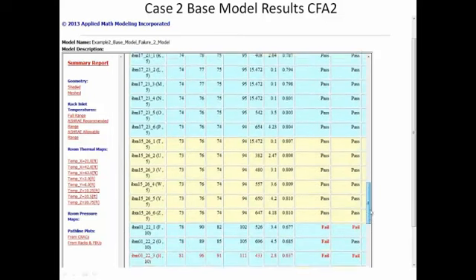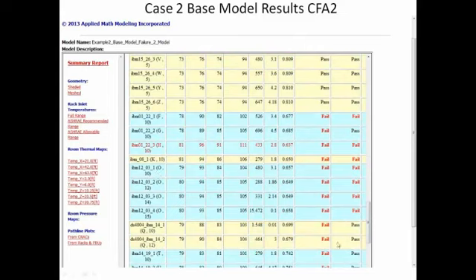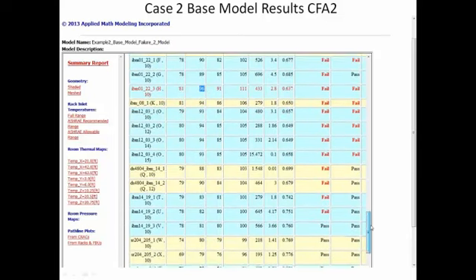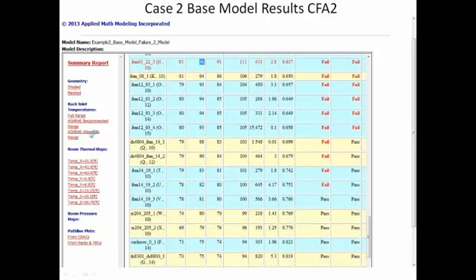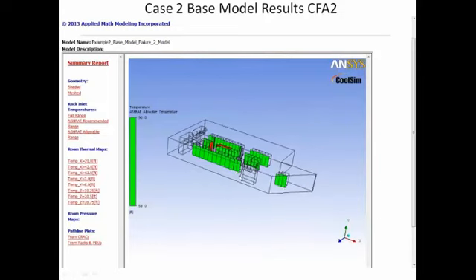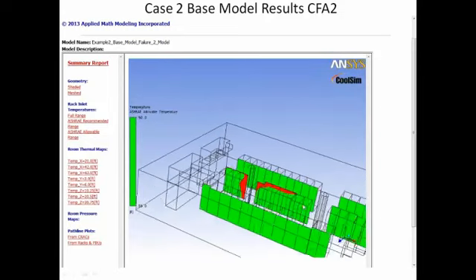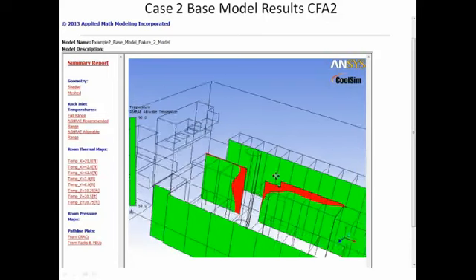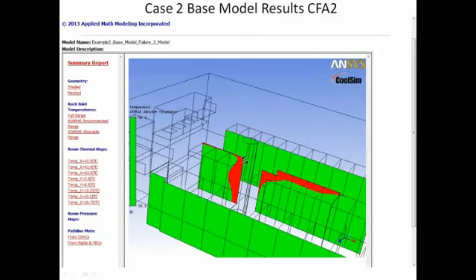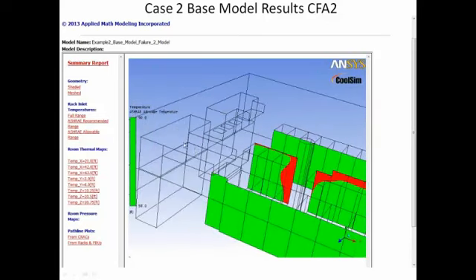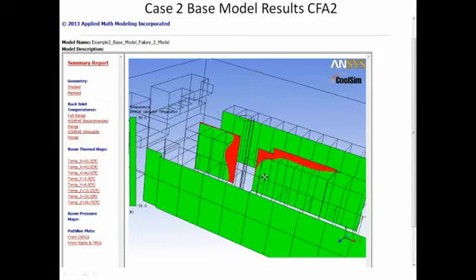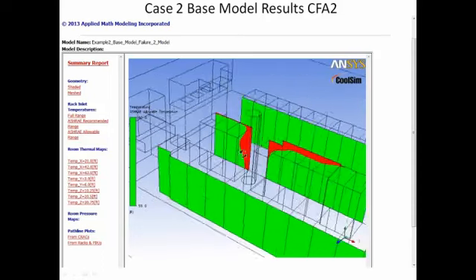So if I go down and take a look at my report, I'm going to find a lot of failures here. My highest rack inlet temp is 96 degrees, which is not a healthy thing. I don't even think I'm falling within my allowable. Yes, look, I'm not even falling within my allowable range, which is up to 90 degrees. So we've got problems in this data center. If this unit goes down for any reason, maintenance, belts, any reason, this data center is going to be extremely hot.